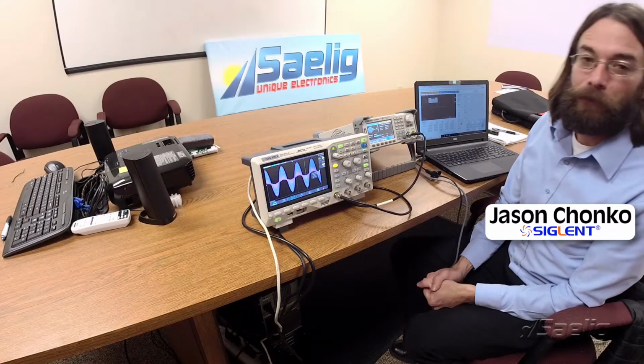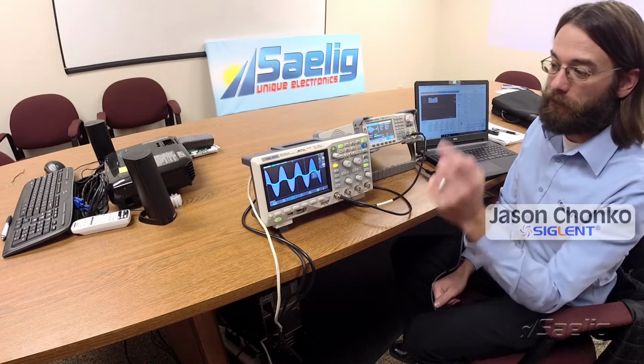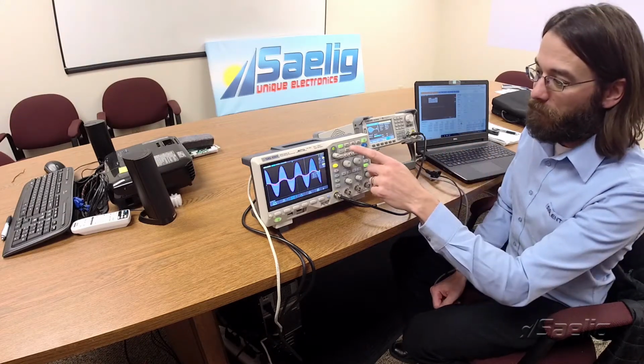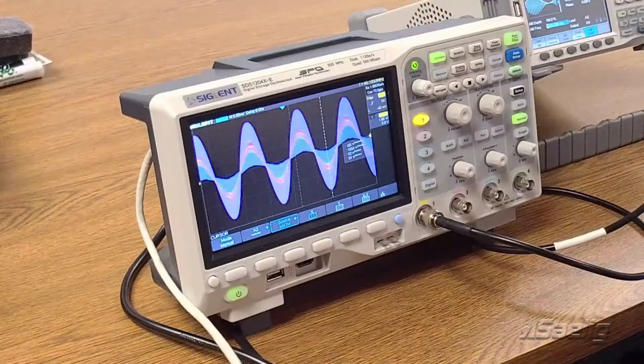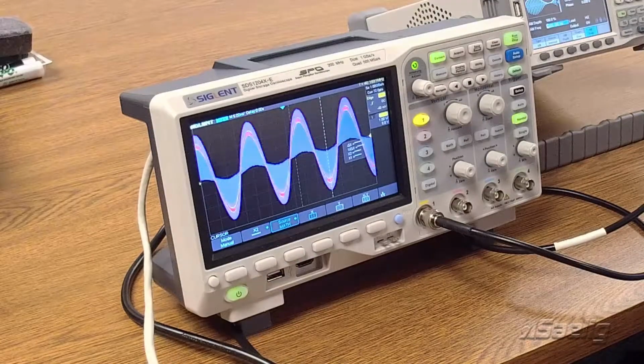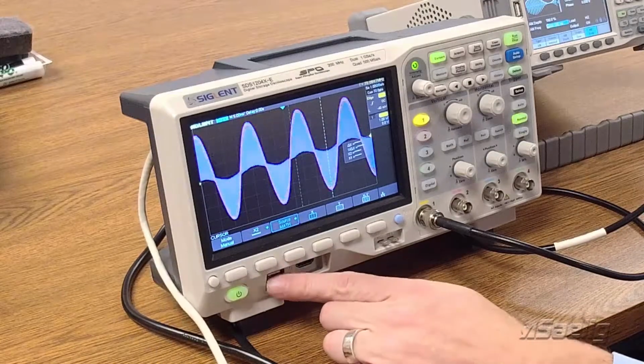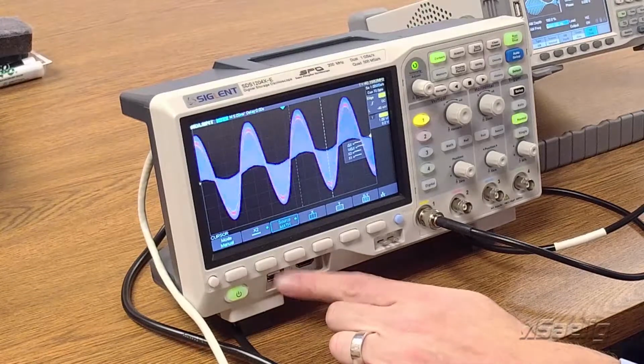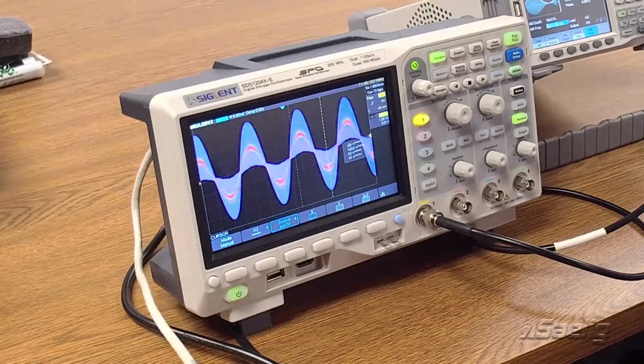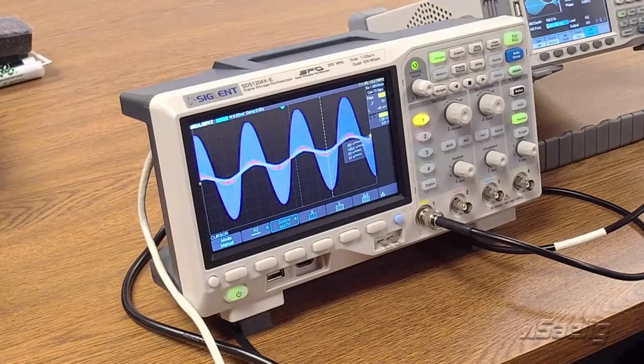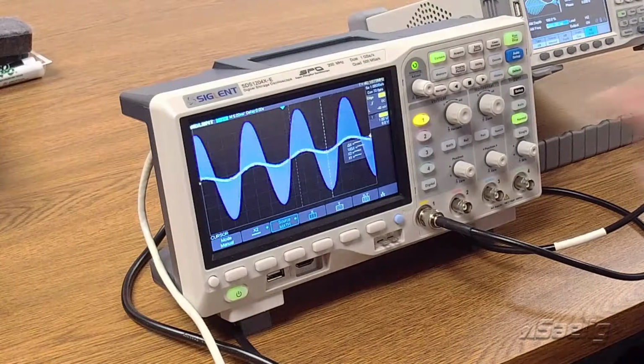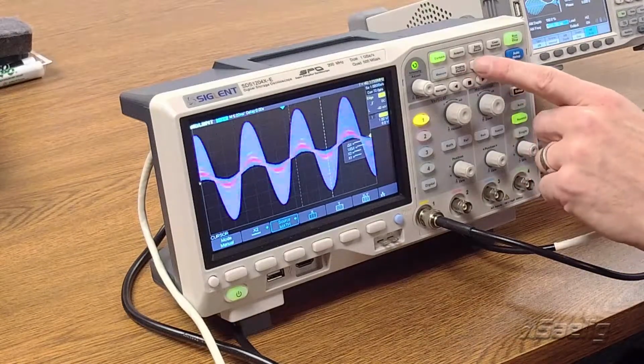So now I'd like to show one of the newest features in this particular oscilloscope, and that is the onboard web page. In order to get that, the first thing we need to do is connect the oscilloscope up to a network. In this case, we're hardwired. We also do have a Wi-Fi connection capability or option, but in this case, we're hardwired into the local network. We've got our laptop connected to the local network as well, and we're going to get the IP address first.